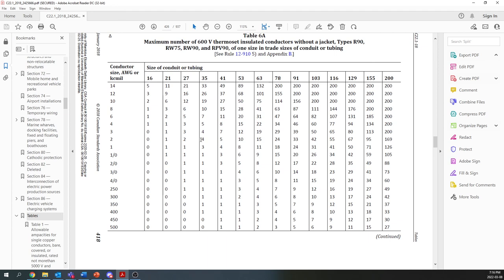So three number twos, we're looking at least a 35 millimeter trade size conduit. And for comparison, two number fours, we would need at least a 27 trade size conduit. So this is half inch, three quarter, one inch, one and a quarter, one and a half, etc. That's the metric to imperial trade size conversions. So we know that, well, so now what do we do?